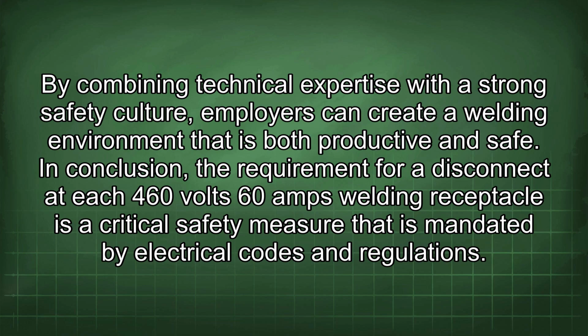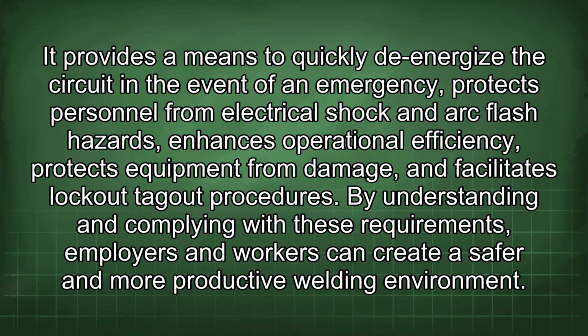In conclusion, the requirement for a disconnect at each 460-volt 60 amps welding receptacle is a critical safety measure that is mandated by electrical codes and regulations. It provides a means to quickly de-energize the circuit in the event of an emergency, protects personnel from electrical shock and arc flash hazards, enhances operational efficiency, protects equipment from damage, and facilitates lockout-tagout procedures. By understanding and complying with these requirements, employers and workers can create a safer and more productive welding environment.